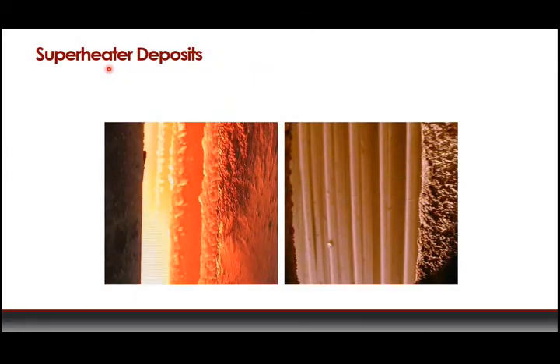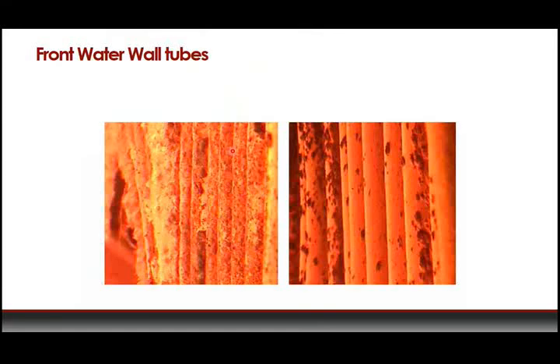A typical melted, sticky black ash is a low temperature ash formation with a melting point of only 600 degrees. Since boiler and superheater areas are typically operated at temperatures higher than that, this ash is most likely always to be in a semi-liquid state — meaning it sticks to surfaces and provides an excellent sticky surface for other materials to adhere. Compare that to an ash with a 900-degree melting point formed by introducing magnesium treatment into the heavy fuel oil. This dry, friable ash has a higher melting point, so it's much less likely to be semi-liquid in any area of the furnace. It's more powdery, more likely to prevent other things from sticking, and more likely to fall off on its own — meaning the boiler is easier to clean.